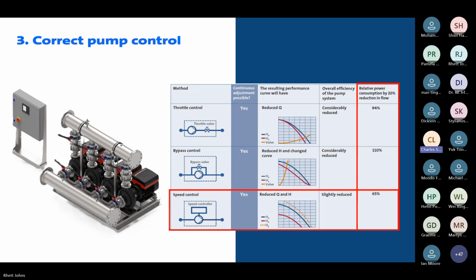And if you look on the right hand side of this where we've highlighted, you can see the relative power consumption, and this is based on a 20% reduction in flow. So if we reduce the flow, and we're comparing all three of these methods, you can see through speed control the power consumption is well below the other methods, and that's because we're only using the power that we need based on the demand of the system.